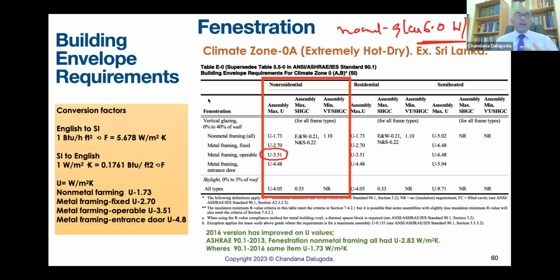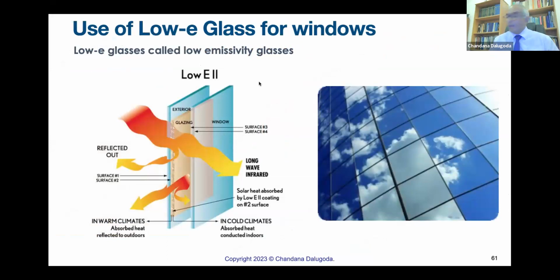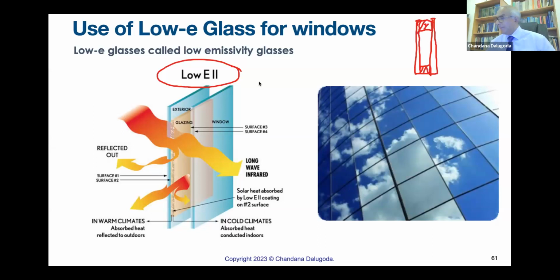Not only that, we will have to reduce the solar heat gain coefficient, and then we'll have to reduce VLT over SHGC. What we do is use low E glasses. What is low E glass? Low emissivity glass. It has two panes and air inside. If this is outside and this is inside, you have a lamination on the outside surface. You can see exactly here: this is the outside pane, this is the inside pane, and the inside lamination reflects most of the energy, the UV rays. If something is absorbed, that will also be reflected. So for most green buildings and maybe net zero buildings, you will have to have low E glasses.